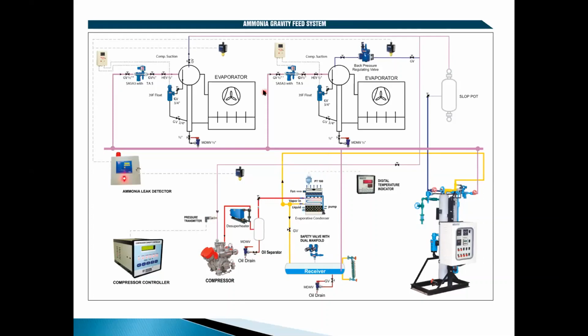Then liquid is fed into the individual evaporator through a solenoid valve and a hand expansion valve. The function of the hand expansion valve is to reduce this high pressure to the pressure corresponding to the temperature you require in the evaporator. Normally, the evaporator is provided with a float switch or level controller, which makes sure that the evaporator is fully flooded. The level controller will sense the level and operate the solenoid valve, giving an on-off signal to your solenoid valve.